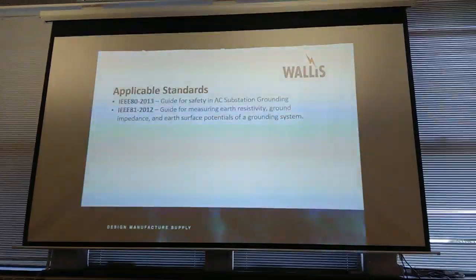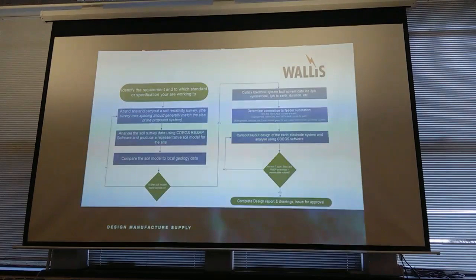Again, sometimes you may come across these. There's some good information in them, but not something you probably see in the UK. That is a little flow chart of the process we use when we're going out doing these earth electrode system designs. You need to know a lot of information before you start doing your designs. You need to know fault clearance time, fault levels, geology of the ground, where the earth system's going, and a lot of other stuff besides.